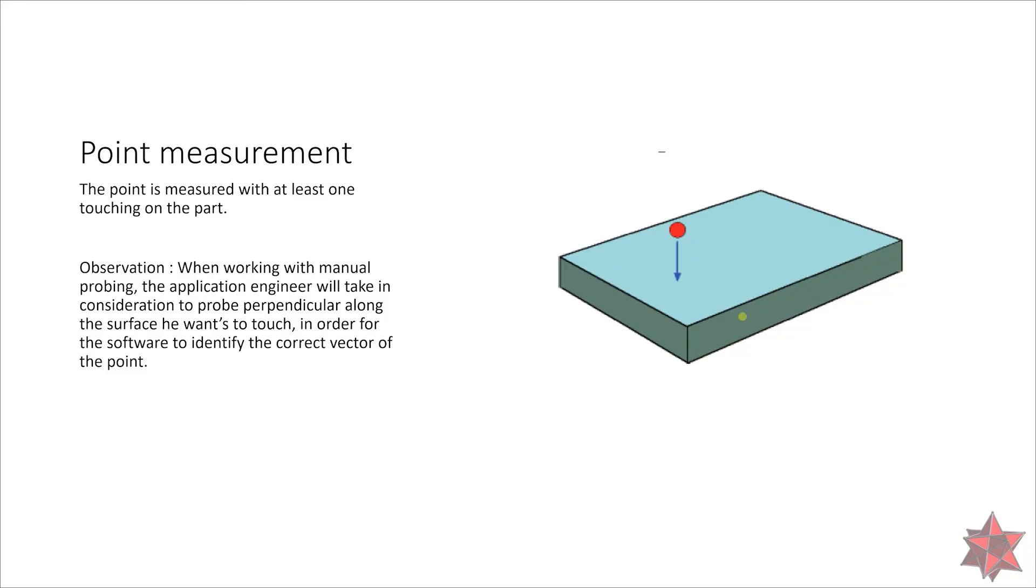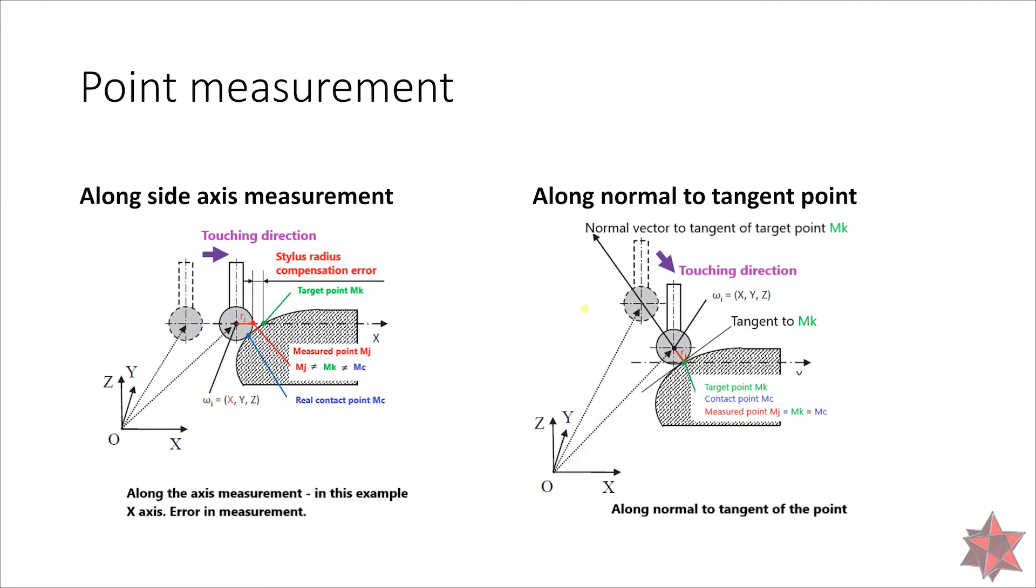I made a short presentation to better explain how to measure a point on a CMM. In this slide we can see that we have to touch the surface at least one time in order to generate the point. When you are working with manual probing, you will have to take into consideration the probe perpendicular along the surface that you want to touch in order for the software to identify the correct vector of the point.